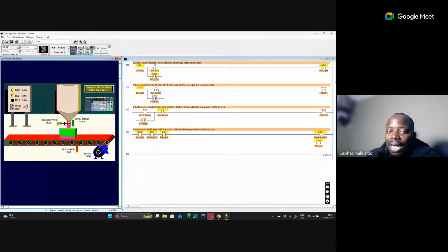Now, fundamentally, we agreed that if you energize a normally closed contact, it opens. Okay? So what that means is that by means of this upper rung, or these upper instructions like this, if you follow my cursor from here to the proximity sensor to the output, the motor will disconnect because this is a normally closed contact. As soon as the proximity sensor is high, this is going to be disconnected. That's what's happening. So we have solved the first part.